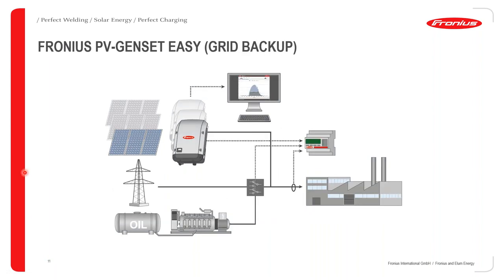The easy solution can also incorporate the grid. When the grid is online, the Fronius PV inverters reduce the power drawn from the grid, and you can also feed power to the grid. The controller supports zero feed-in and a percentage feed-in threshold. When the grid goes down, the genset becomes the voltage and frequency reference for the Fronius inverters. The controller then prevents back feed to the genset and throttles down the PV inverters to always maintain a minimum genset running load.